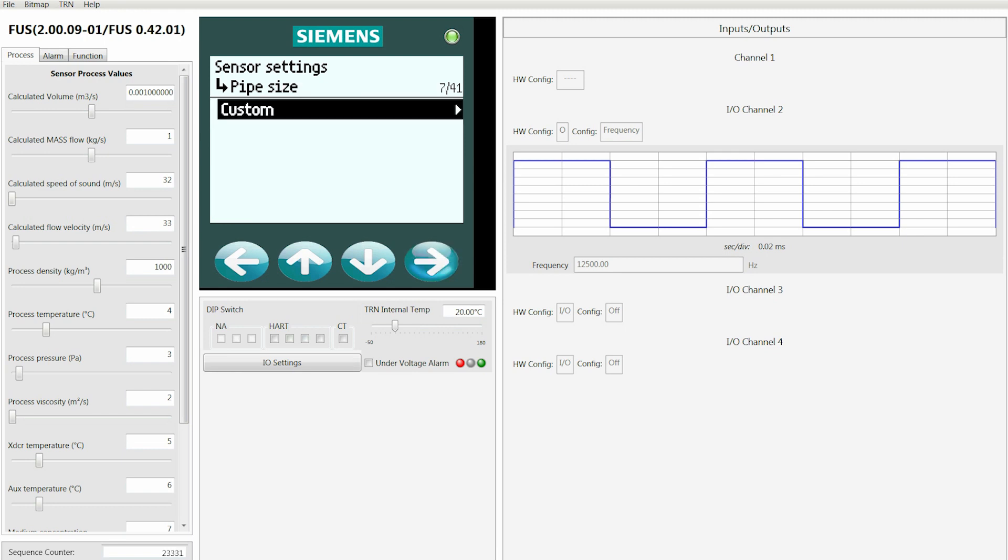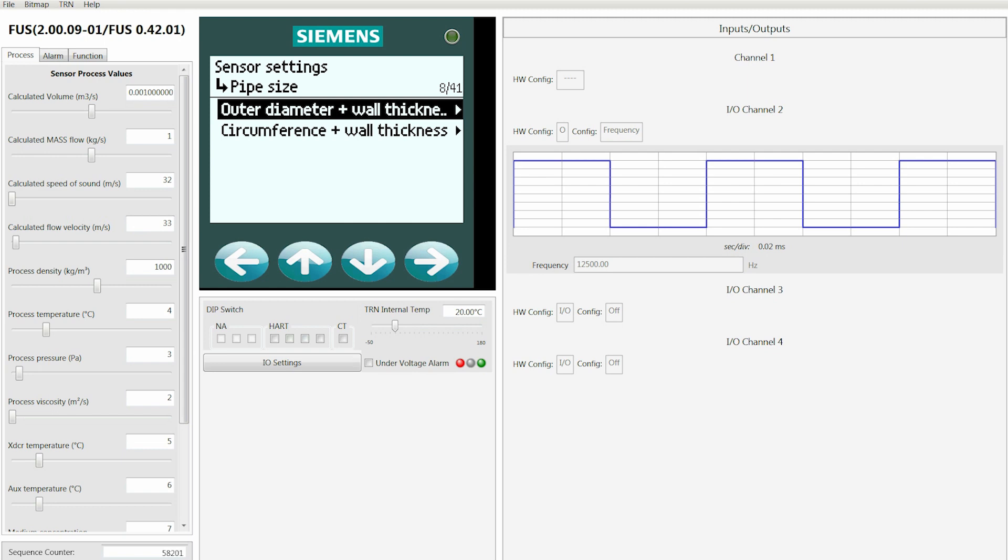Here we're going to move down through the various materials and we're going to select Custom, then hit the right arrow one more time. Once you get in the custom screens, you've got a couple of choices. You could work with either the outer diameter and the wall thickness, or you can work with the circumference and the wall thickness. We're going to select outer diameter and wall thickness.